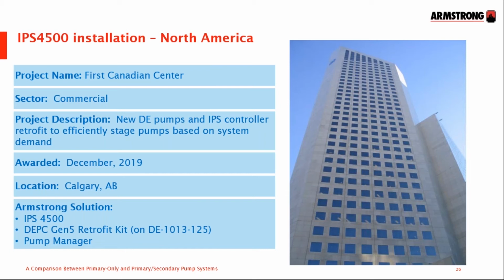Armstrong initially installed a design envelope pump in 2016 as part of an energy upgrade project, and then in 2019 two further new design envelope pumps were added to the system, and the 2016 pump was upgraded to the latest generation 5 with its design envelope pump controller, all connected and automated by an IPS 4500, which provides intelligent multi-zone control, integrates with the BAS, delivers optimal energy performance, and stages them according to best efficiency. And those are 125 horsepower units, 3 of them.